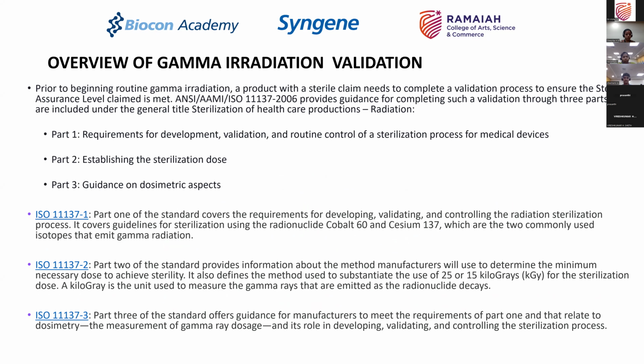A product with a sterile claim needs to complete a validation process to ensure that the sterility assurance levels which we are claiming are being met. Now, there is a guideline, ISO 11137-2006, which provides the guidance for completing such validation through three parts that are included under the general title Sterilization of Healthcare Products by Radiation. So this is an ISO guideline which is there.